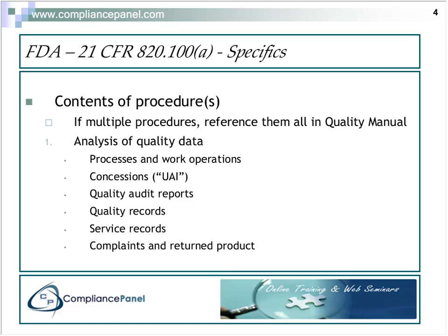That's product that actually has hit the field, as is service records, but service records are more perceived as it just happens. Our product needs servicing, go ahead and send it in. But a complaint, somebody has a real problem with your product. Complaints should be CAPA'd, if you will, on a complaint-by-complaint basis. Each complaint should be analyzed to determine what type of investigation is required and what type of corrective action is required.